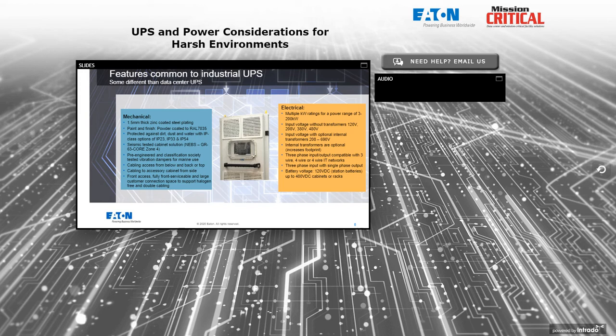And the question is, can the UPS run from that DC voltage, or does it need a different voltage like 240, 120? Small UPS might be 12 or 24 volts, but 120 and 125 volts DC are very common. Typical larger UPSs use a 480 volt DC input. These are the kind of things that might change in an industrial rated UPS.